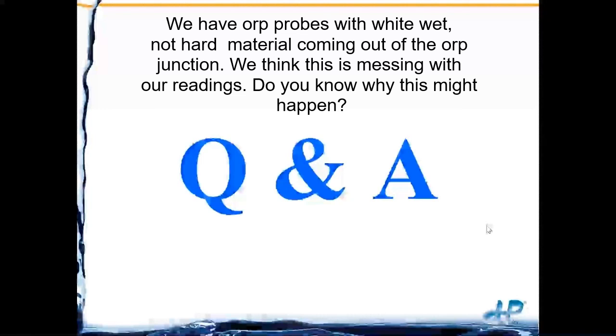Question: we have ORP probes with white, wet, non-hard material coming out of the ORP junction — we think this is affecting our readings. My guess is it's the KCl solution coming from inside the probe out to the junction, where it's reacting with your process.